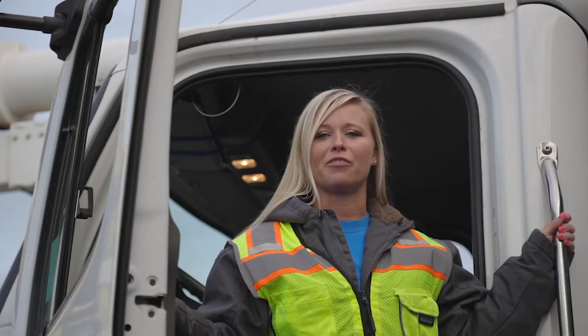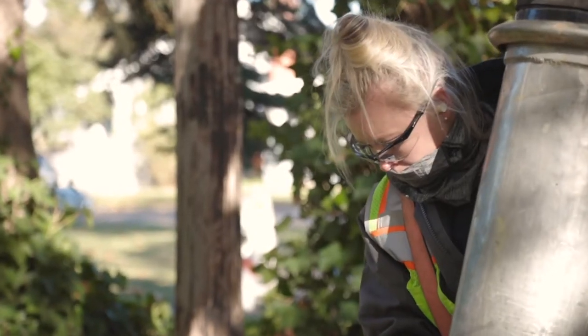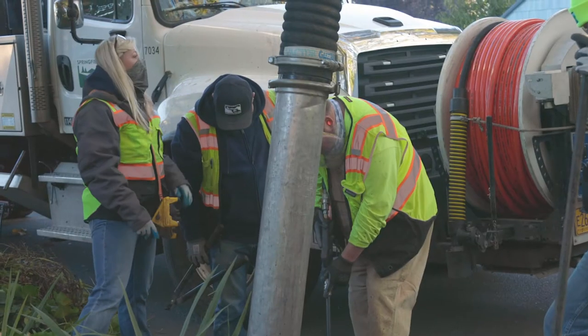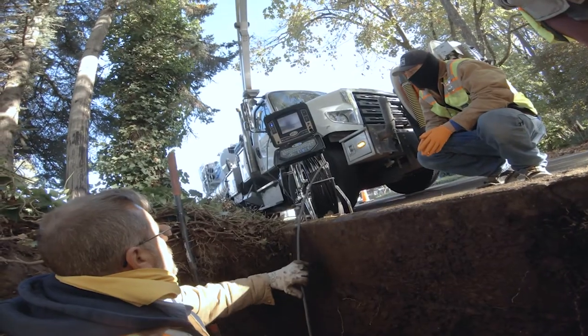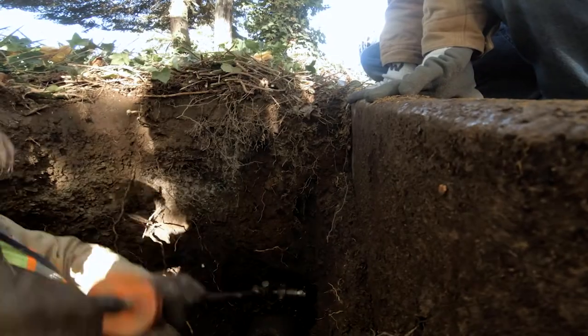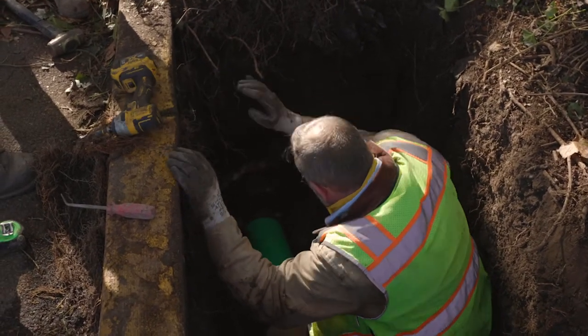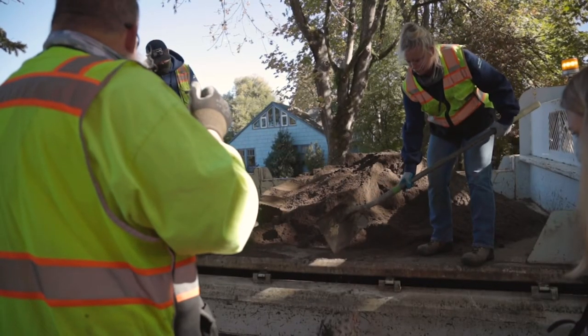Once we've identified sections of pipe that need to be focused on first, it's time to get to work. Today, we took our Vactor truck over to the historic Washburn district to repair a leaking section of wastewater pipe. We dug down to the top of the pipe using the Vactor truck to vacuum up soil and roots. Once we reached the top of the pipe, we spotted the problem — roots had grown into the pipe over time, creating a large hole. We used a chain pipe cutter to remove the leaking section, replaced it with new PVC pipe, and used fittings to connect the new pipe to the existing pipe. Then we filled the trench back in using sand to hold the wastewater line securely in place.